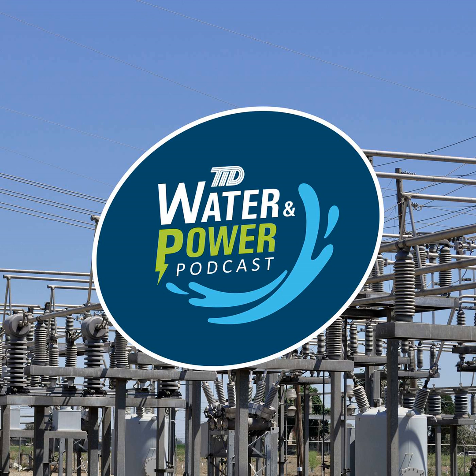To do that required investing in a new transformer, which is a very hefty cost—somewhere between $2.5 million and $3 million per transformer. So it's very important that we provide good protection to the transformer, thinking about it from a risk assessment standpoint, making sure there's fire protection or consideration in case something were to happen to one transformer—we definitely wouldn't want that to happen to a second transformer.